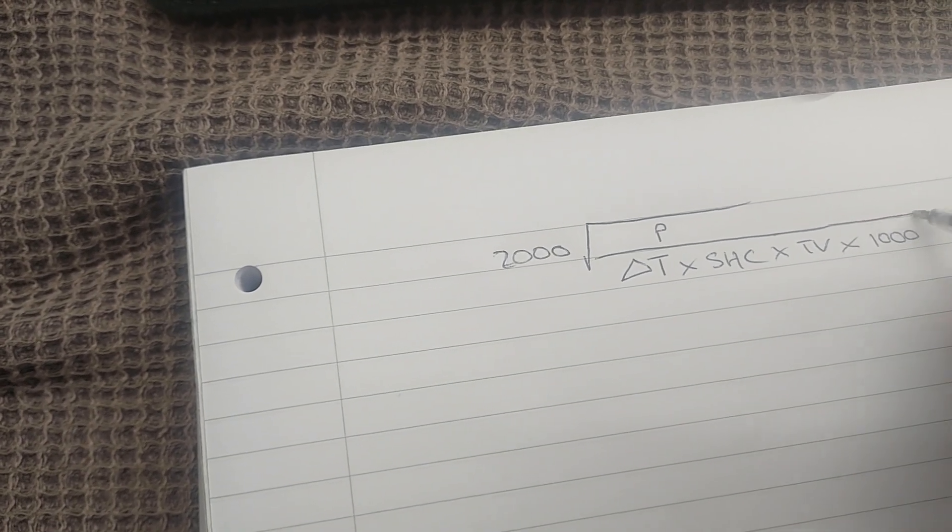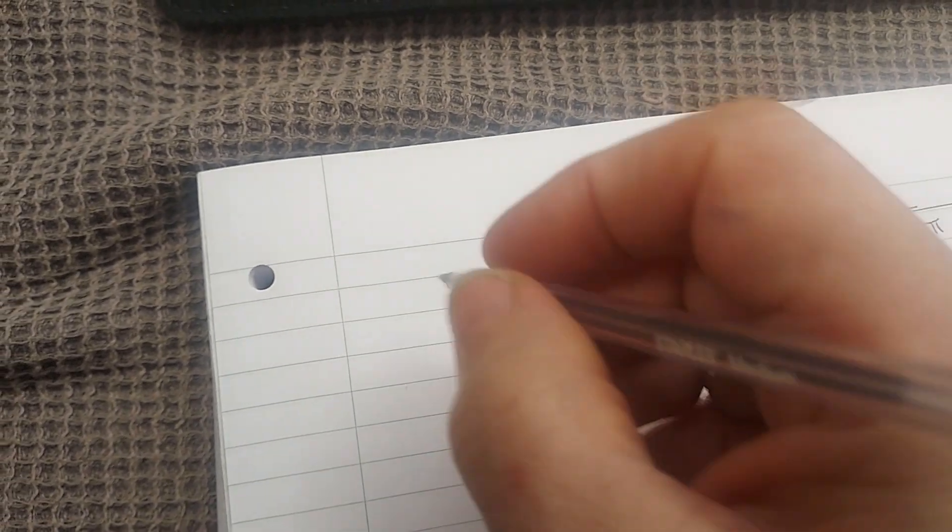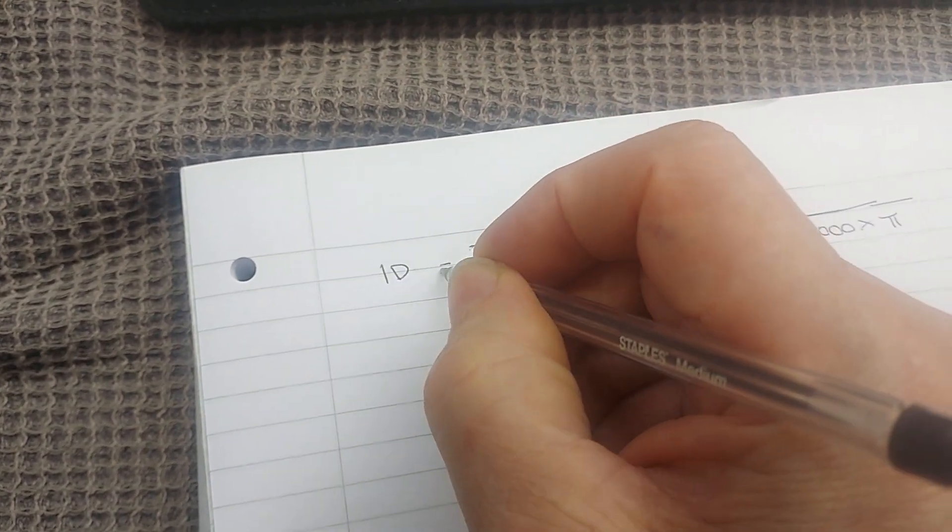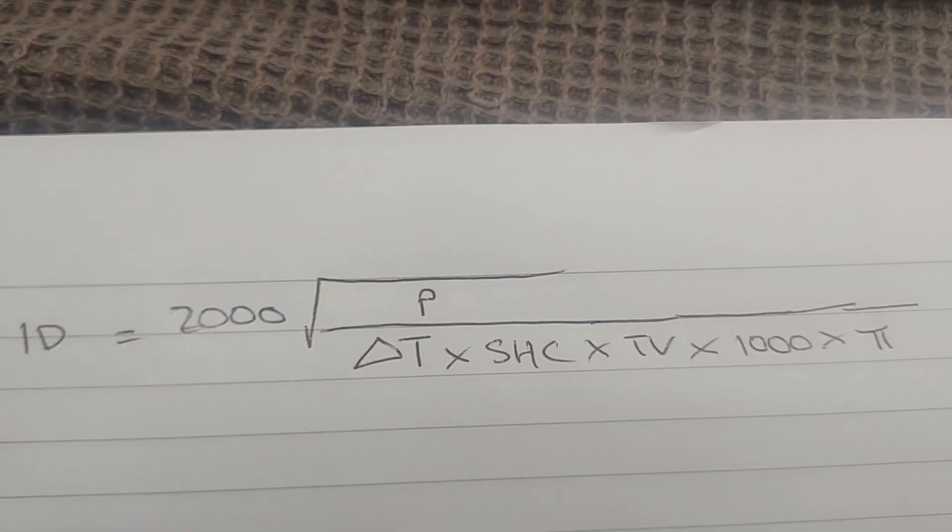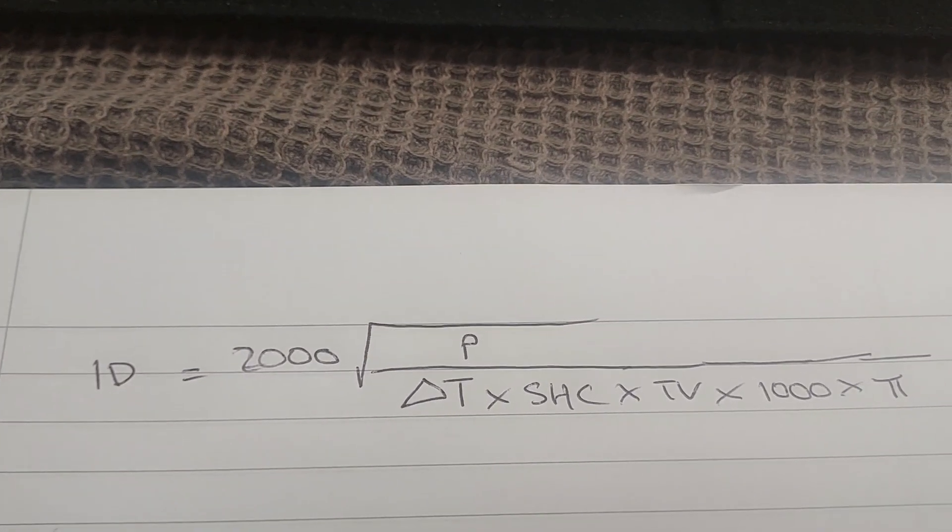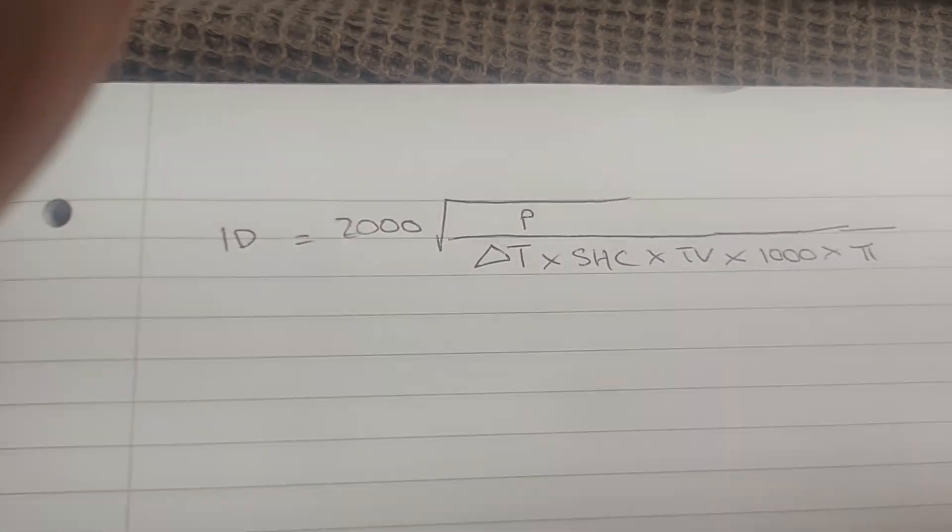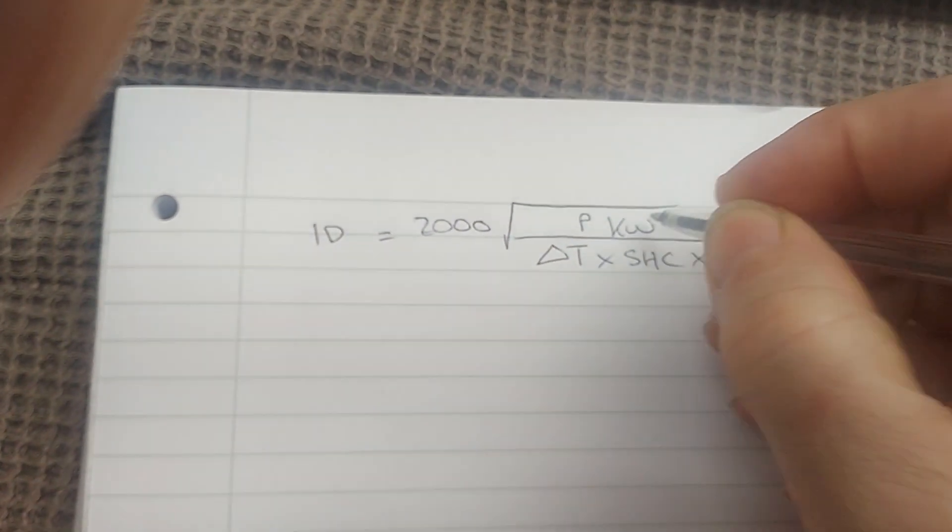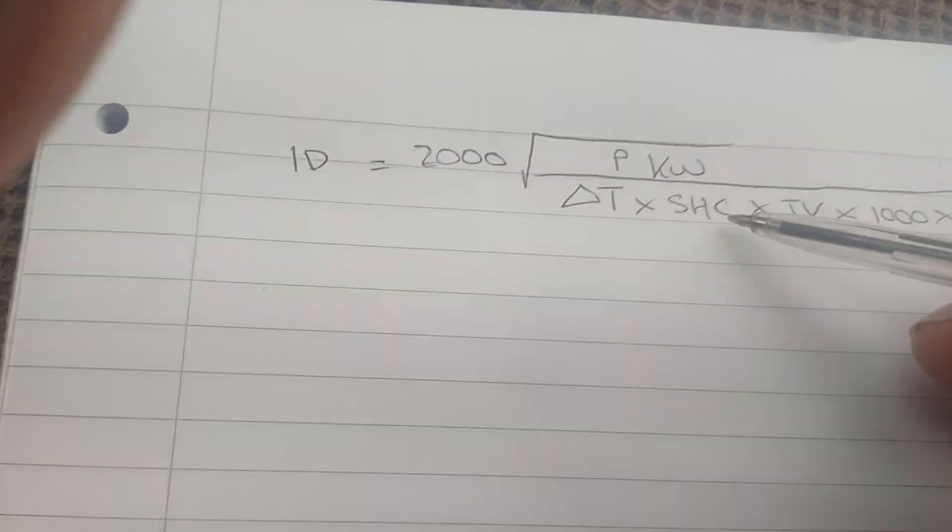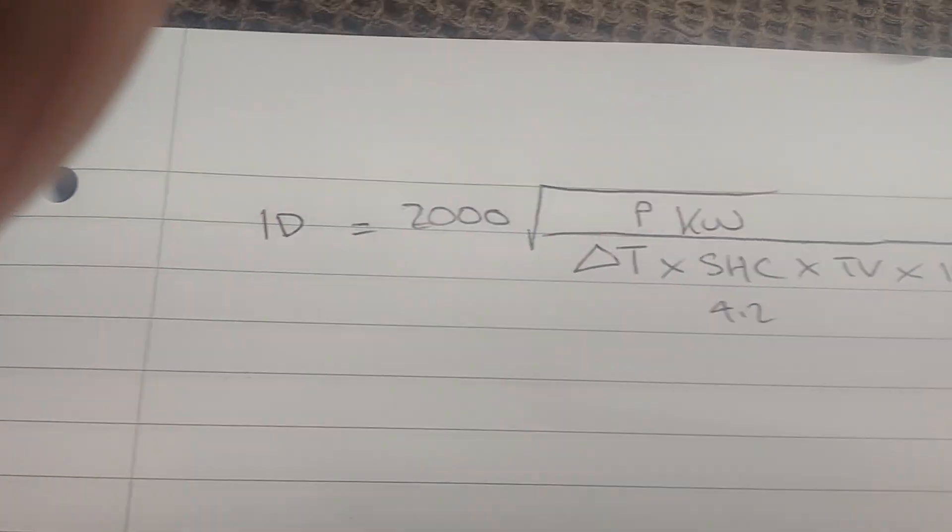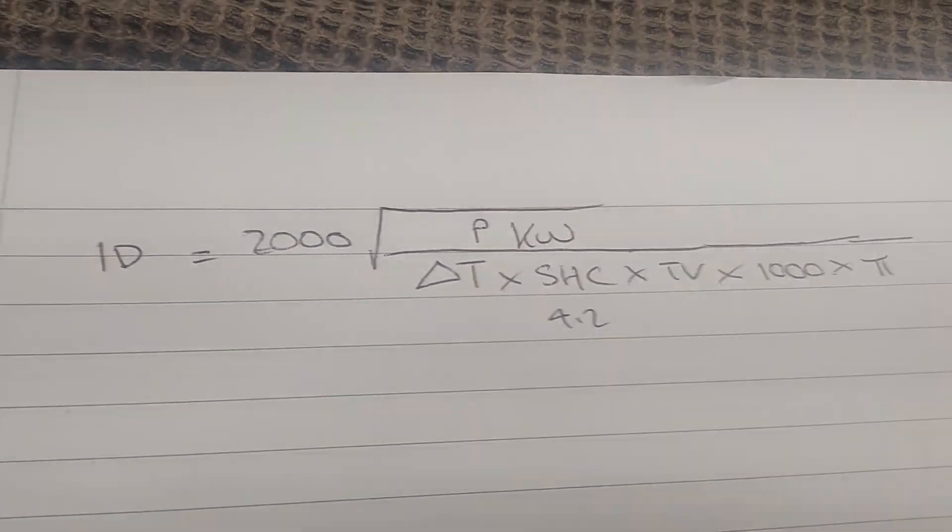That will give you the internal diameter of your pipe. Now you need to add some brackets, and if you're going to stick it in your calculator you'll need some brackets to be added to that. Power obviously is in kilowatts, and our specific heat capacity will be 4.2.